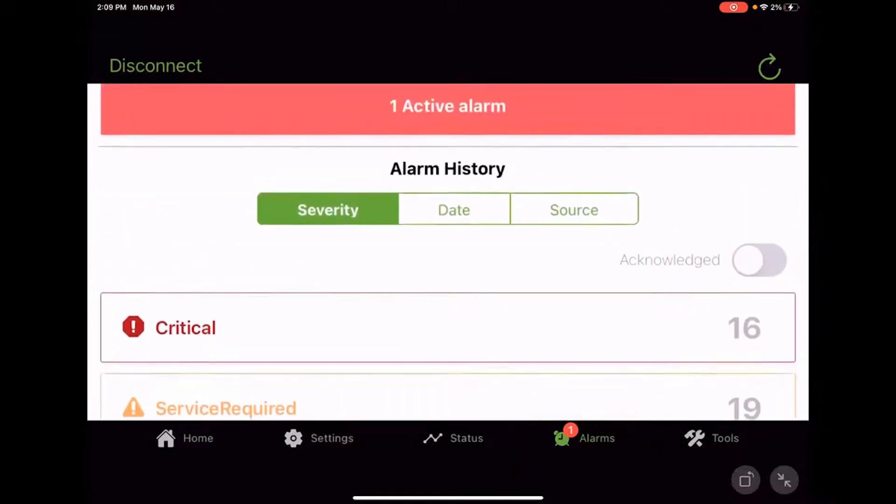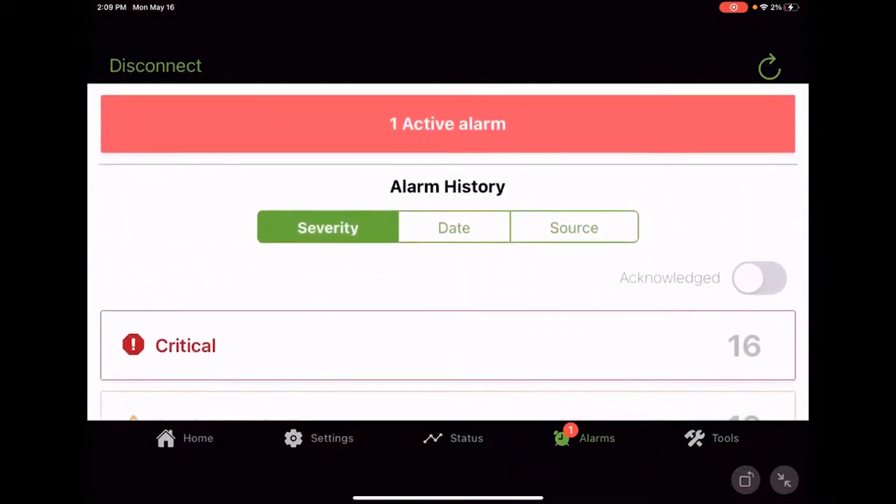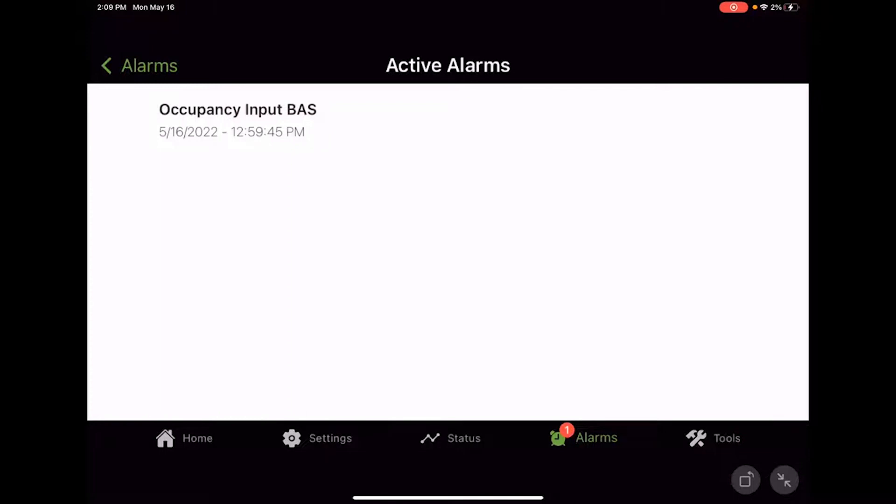And here we have the alarms page, and at the very top, we've got one active alarm, and we could just simply click on that, and our occupancy input BAS has an alarm going on because it's not seeing the state that it wants to see right now. So we would need to go and see what's going on with our occupancy input from the BAS system.